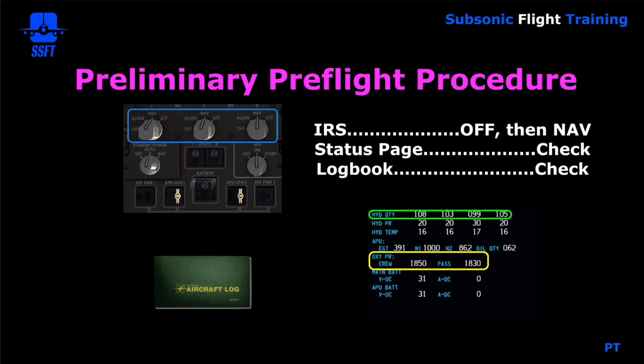On the status page, we check hydraulic quantities to make sure they're sufficient. 1.00 represents a normal service level. It's a percentage, not gallons or liters, of the normal service level, so 1.08 means 108% of normal. Full is around 1.18 to 1.19. Anything at 0.99 is slightly below normal, and anything above 1.00 is above normal. The refill indication comes at 0.75 or less, so as long as you don't see an RF there, you have enough hydraulic quantity. Normally you'll see readings like 101, 102, 103, or 0.99, like here.